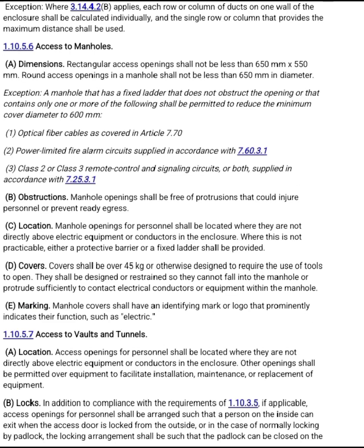1.10.5.6 Access to manholes. A. Dimensions. Rectangular access openings shall not be less than 650 mm x 550 mm. Round access openings in the manhole shall not be less than 650 mm in diameter. Exception. A manhole that has a fixed ladder that does not obstruct the opening, or that contains only one or more of the following, shall be permitted to reduce the minimum cover diameter to 600 mm. Number 1. Optical fiber cables as covered in Article 7.70. Number 2. Power limited fire alarm circuits supplied in accordance with 7.60.3.1. Number 3. Class 2 or Class 3 remote control and signaling circuits, or both, supplied in accordance with 7.25.3.1.